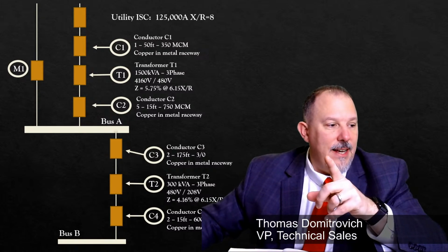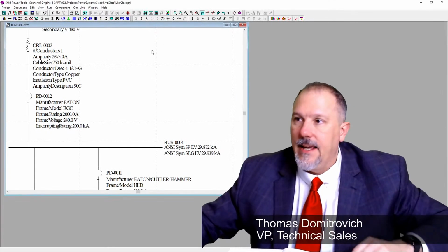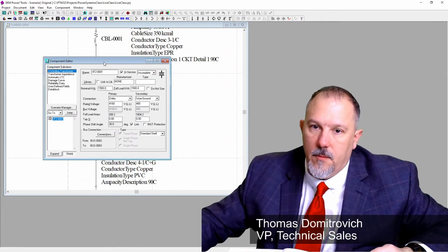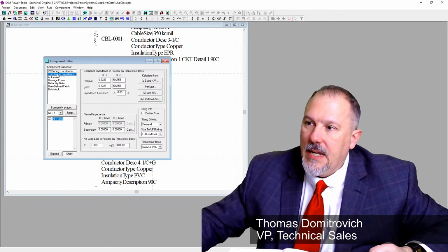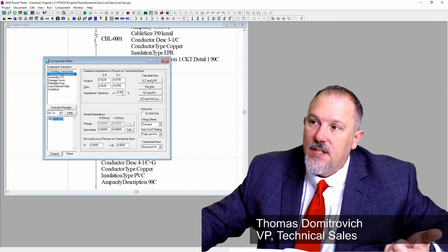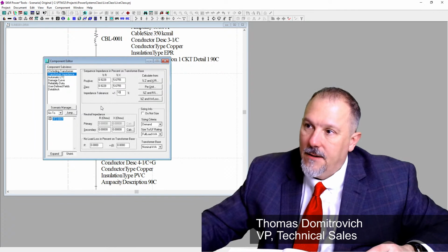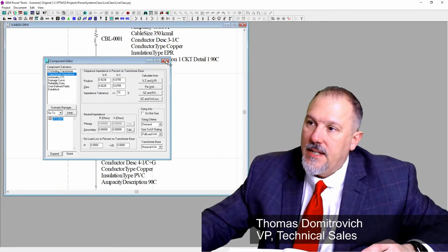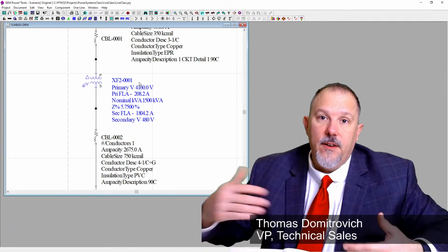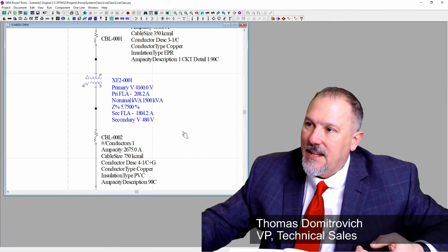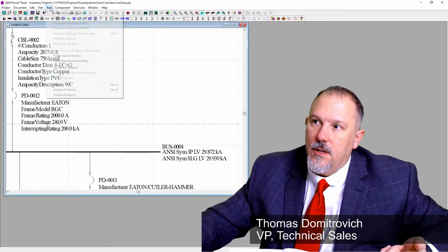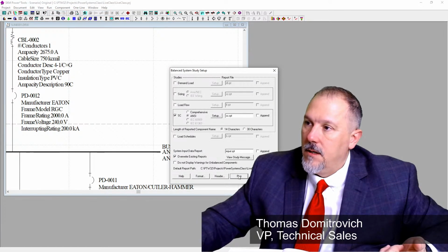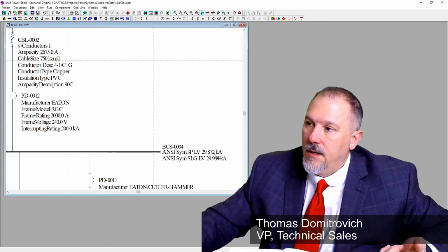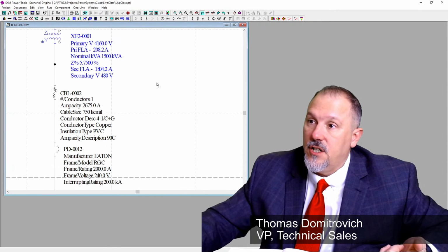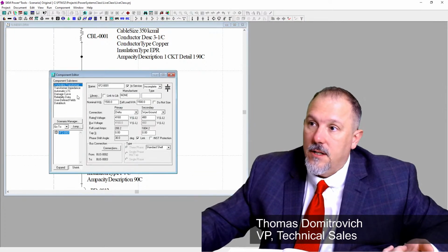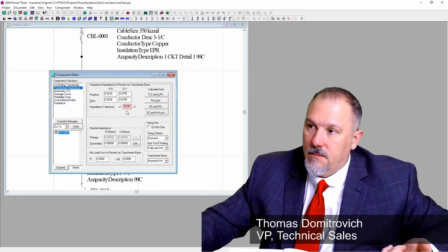The next question is, does SKM do that? So let's take a look at SKM. Let's open up the transformer, and I look at impedances. There it is, impedance tolerance. See, I have 0%. I could put 10% in there. So if I put 10% in there, then it's going to use that for my incident energy. And now I did plus or minus 10%. So what's this? 29,872. I'm going to do a run, balanced system study. 29,872. So it did not use that in my calculation of my bolted fault current, because it should have changed. Let's just make sure I have that done. Plus or minus 10%.